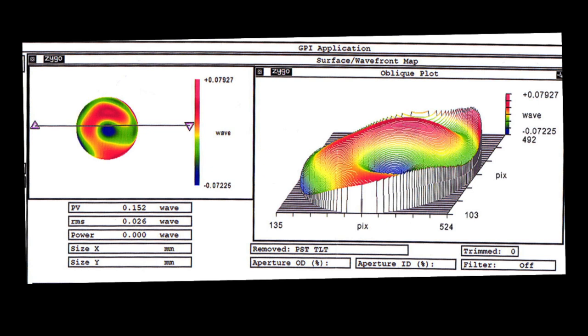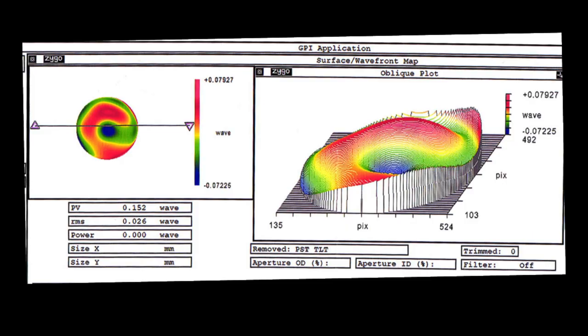So those values describe what is called wave front deformation in optics. This is not something strange, it's very common to have wave front deformation since you cannot make a perfect lens or mirror optical instrument. You can also see the PV and the RMS values here. So if you would have a perfect mirror or perfect lens, you would have a flat plane and those values would be zero. So when we are talking about wave front deformations, the perfect mirror or perfect lens would have a value equal to zero, and this means you have a perfectly flat plane. So the smaller the values here, the better.